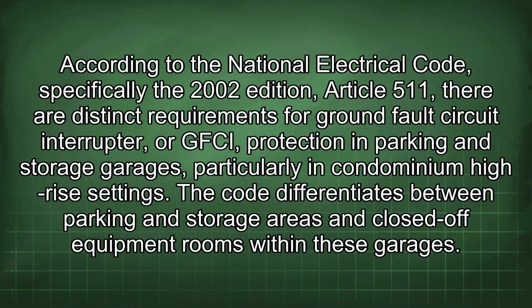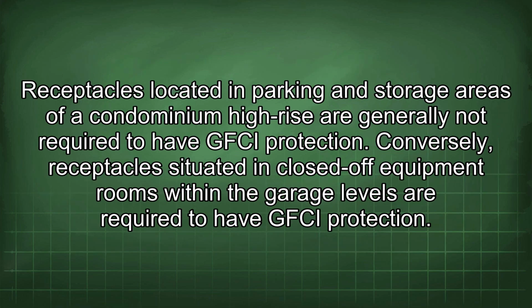According to the National Electrical Code, specifically the 2002 edition, Article 511, there are distinct requirements for ground fault circuit interrupter, or GFCI, protection in parking and storage garages, particularly in condominium high-rise settings. The code differentiates between parking and storage areas and closed-off equipment rooms within these garages. Receptacles located in parking and storage areas of a condominium high-rise are generally not required to have GFCI protection. Conversely, receptacles situated in closed-off equipment rooms within the garage levels are required to have GFCI protection.